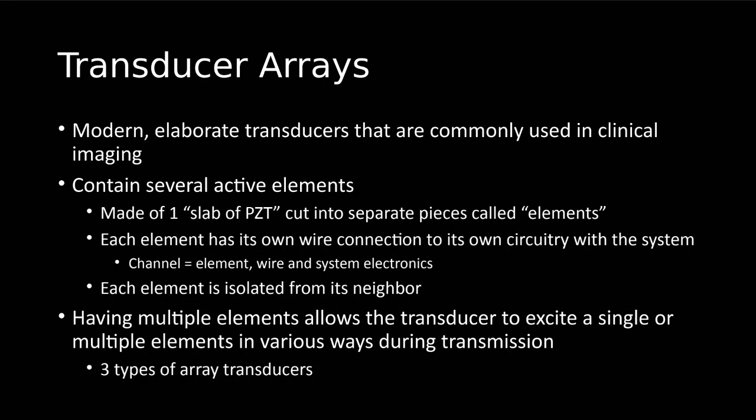And that's how the system is able to automatically steer, automatically focus if we want to change our focus while we're scanning. Because each element, when we're creating that pulse, is going to be excited in a different pattern. And our system can control that, right? So when you have only one piece of PZT, or only one active element or one crystal, it's only going to be able to do one thing at a time, right?